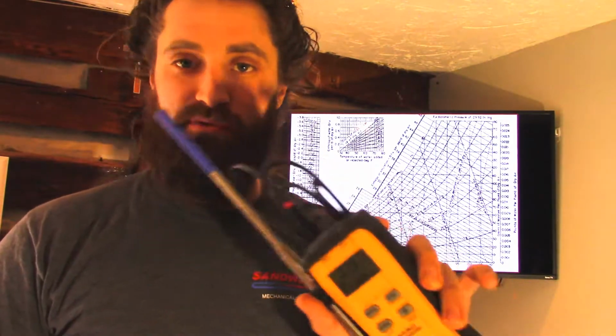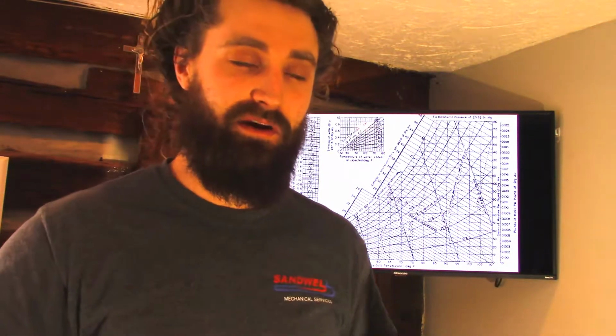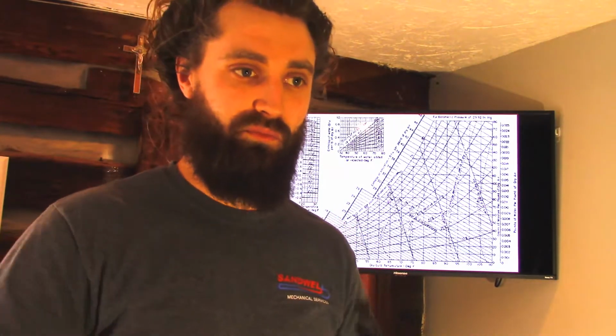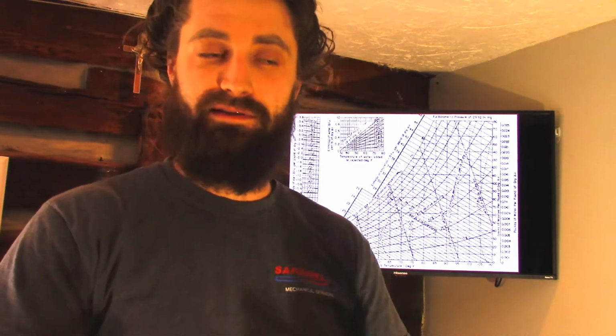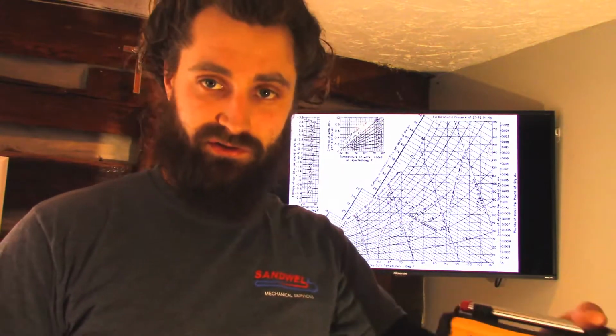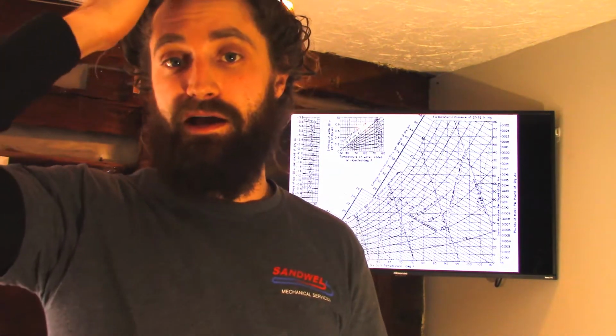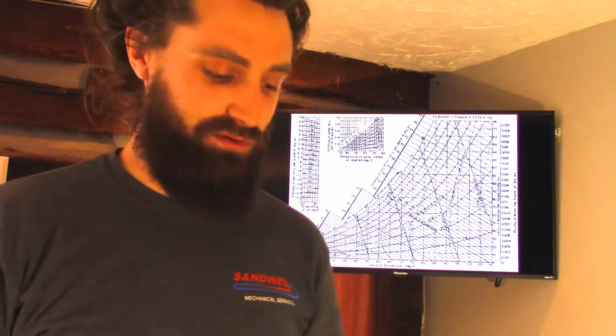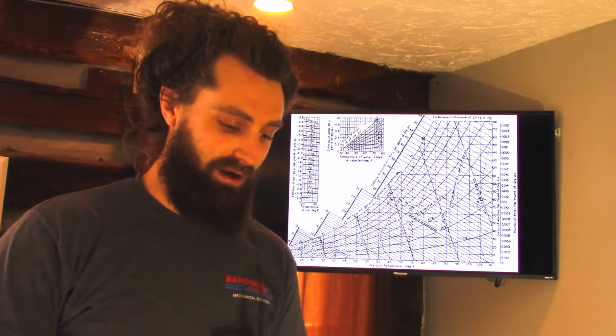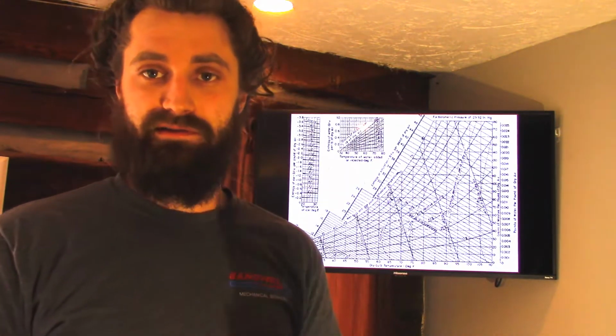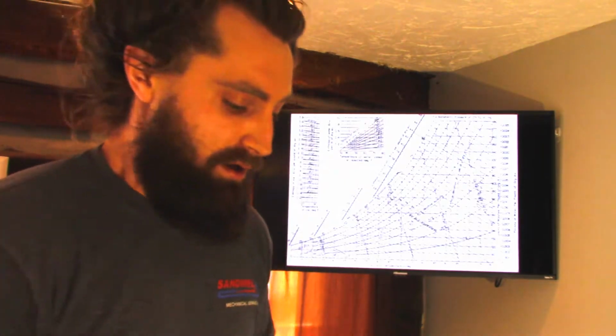I like to go throughout the house and take a few different readings. I'll take a reading at the return, which gives a good idea of how much humidity is in the air entering the furnace, and I'll also take a humidity reading at the supply trunk, either directly at the furnace or at a few of the supplies. Right now, we're in the mid-30s on relative humidity, which isn't bad since it's about 17 degrees outside today.